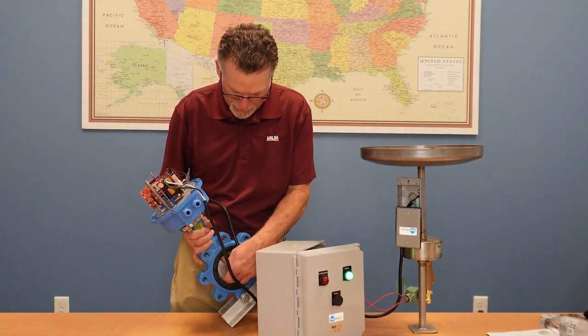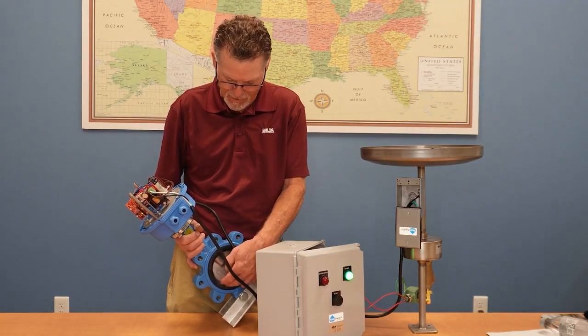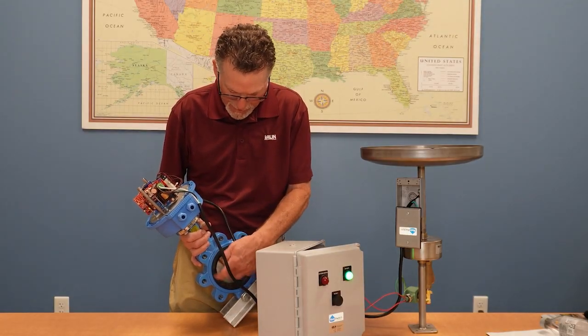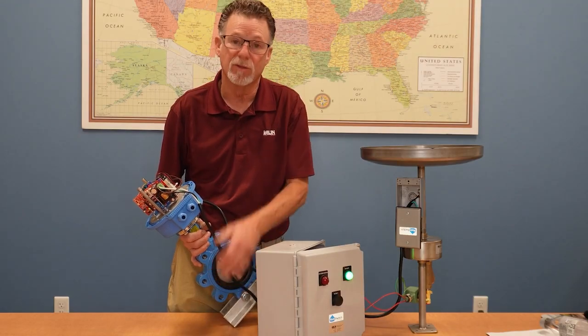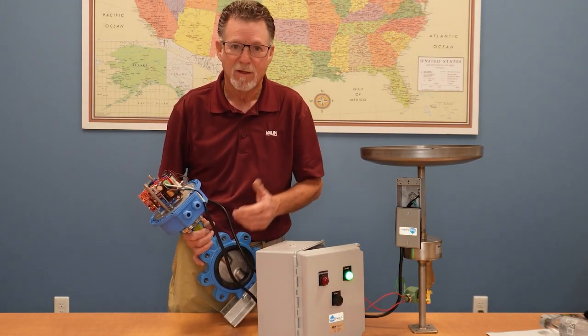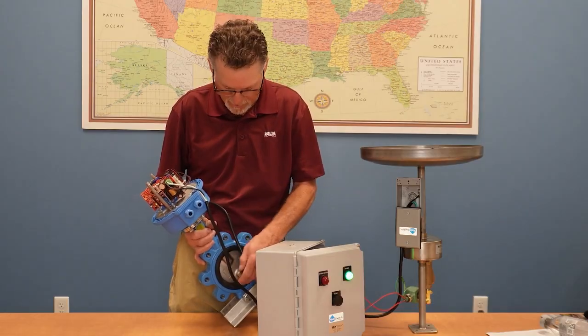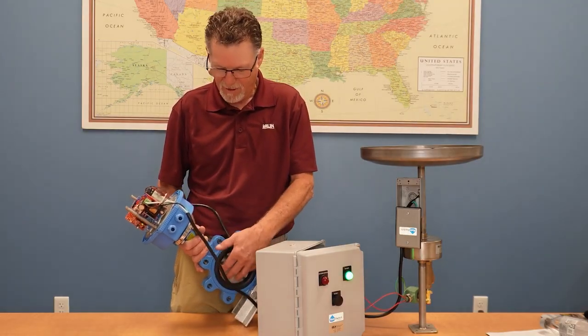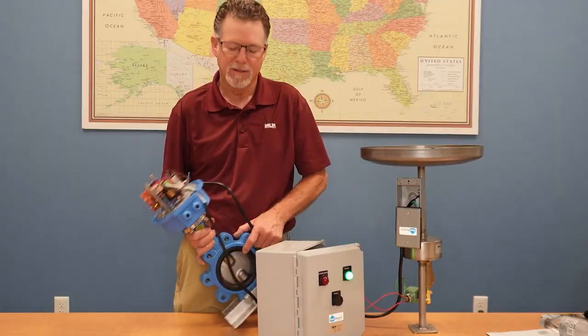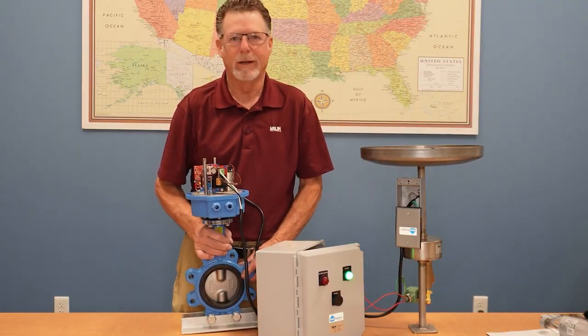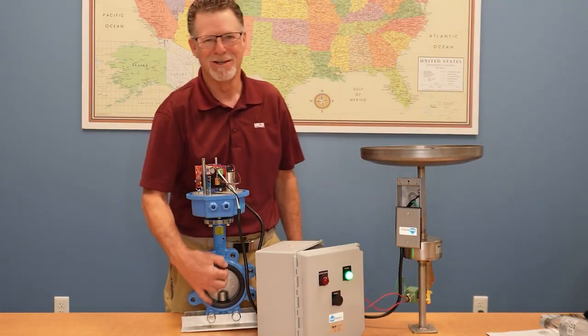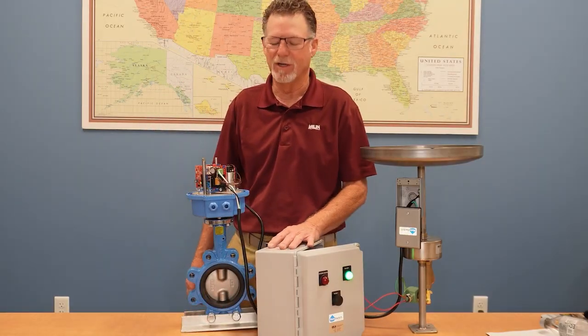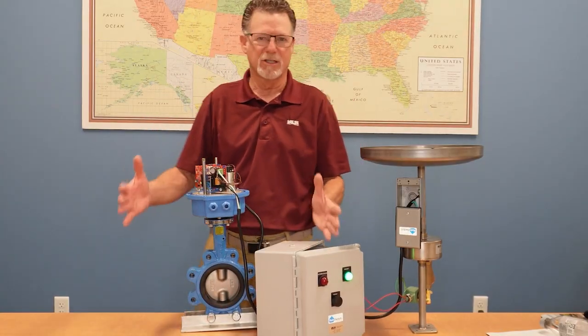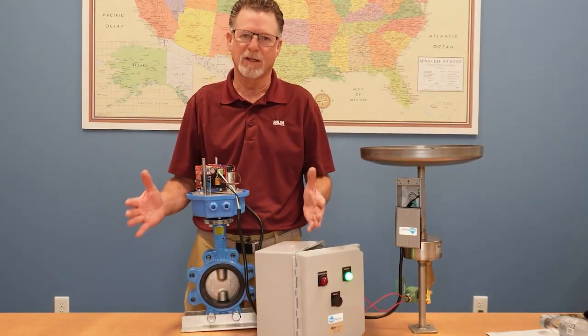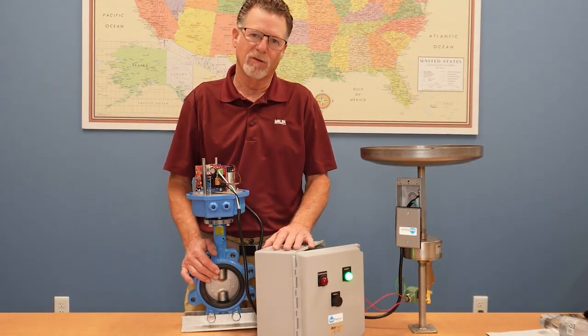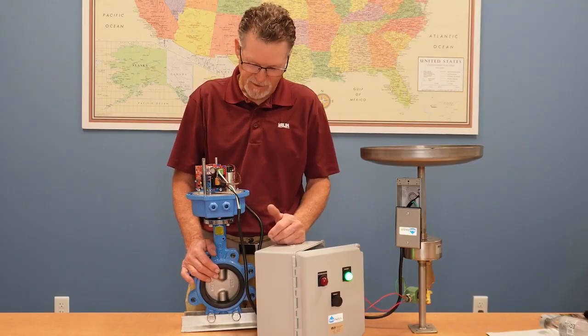As you can see, any debris that's flowing through the system, the butterfly will not obstruct anything from flowing through. I mean, we've seen rags, we've seen branches and leaves get hung up on the butterfly. So if you can get it installed like this, probably 99% of the time it's golden. In the not ideal situation in a vertical, that's just because there's physically not a lot of room in the vault, so they end up getting installed like this.